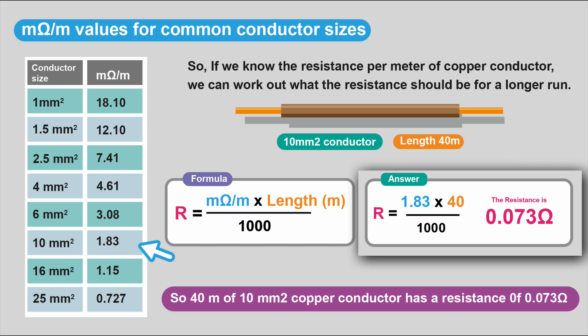1.83 times 40, the length, divided by 1,000 to get it back into ohms. And the resistance of this conductor is 0.073 ohms. So 40 meters of 10 millimeter squared copper conductor has a resistance of 0.073 ohms.